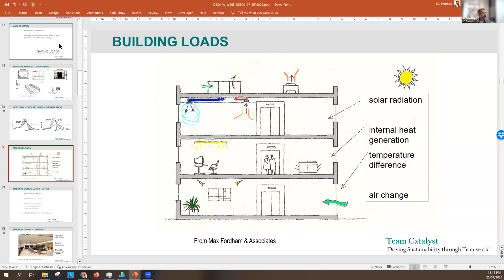But when looking at air conditioning, the engineer is very clear that something called heat gain is instantaneous. If you switch on a 28 watt light, you get an instantaneous heat gain of 28 watts into that space. If you turn on a fax machine, whatever heat it generates is an instantaneous gain into the space. But what the air conditioning system sees is not simply the sum of the gains at any instant, because there is storage and release of heat in the building fabric. That's why we need energy simulation or load calculation methods, because when you add up the gains, they don't translate directly to cooling load.